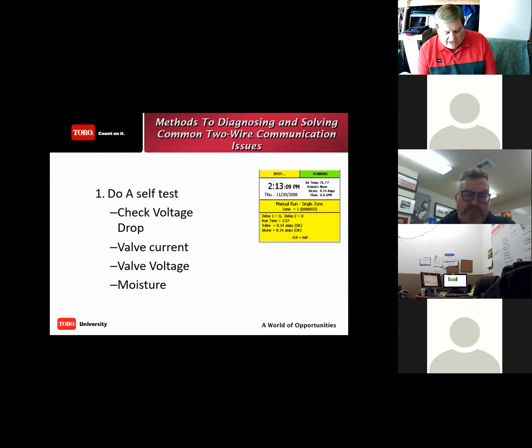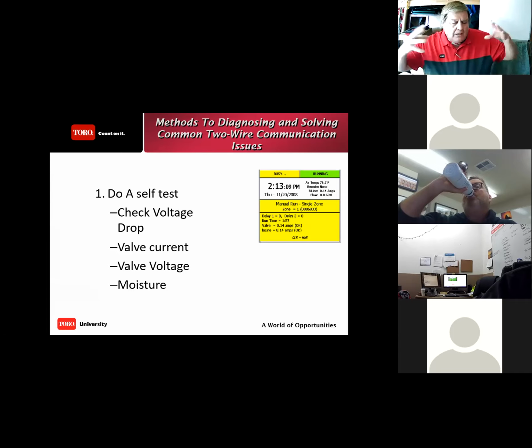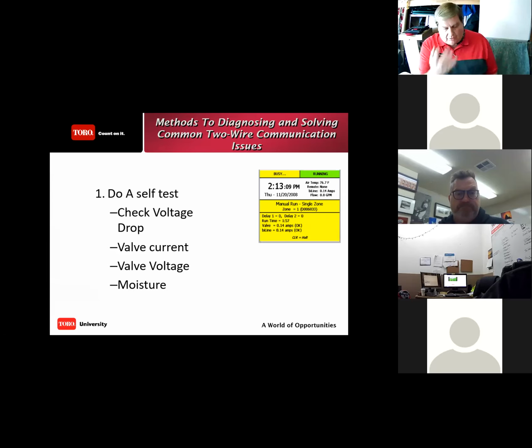A lot of the clock self-diagnostics are very beneficial, and they will tell you whether you have a high current draw and it's shutting it down because it doesn't want to damage the clock, or it'll tell you, I can't talk to zones 1, 7, 9, 13, 24, and 36. If it's not communicating, there's a good likelihood the wire connection has gone bad. Now, we have wire connections a little bit later in the presentation here, but the diagnostics of the clock are very beneficial. Start with it. You're at the clock, start there, do a diagnostics and read what it says. At least that can give you an idea of what you're up against when you go out to troubleshoot.